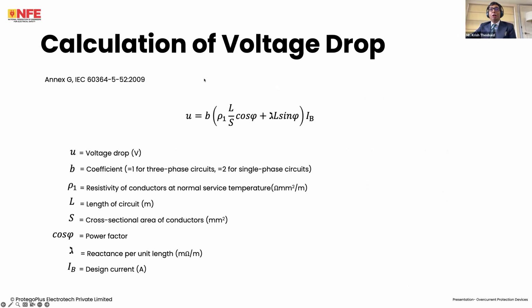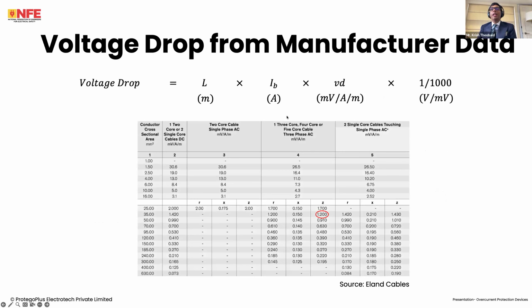There is a far more interesting calculation given in IEC 60364. It's just an explanation of really what is being done here, and it provides you a more, I wouldn't say accurate value, it provides you a more holistic picture of how it is calculated. The manufacturer data is just based on this formula itself. So in the absence of manufacturer data, you can use this formula. But really, if you are using any decent manufacturer's cable or conductor, you will get these values anyway.